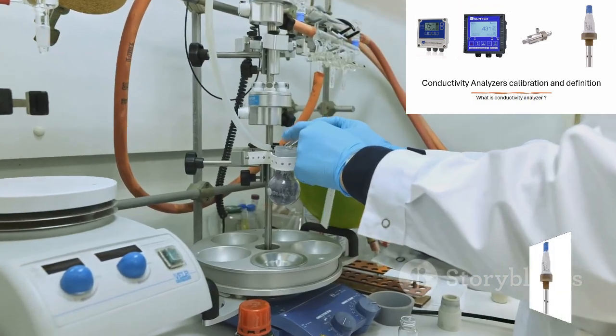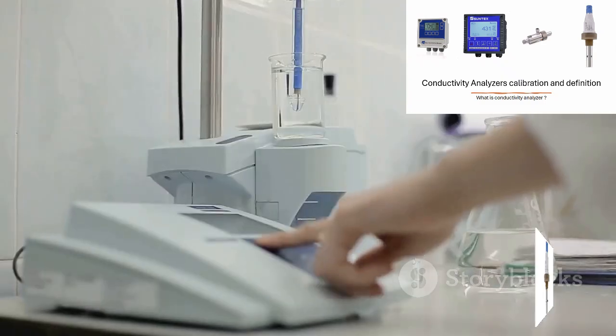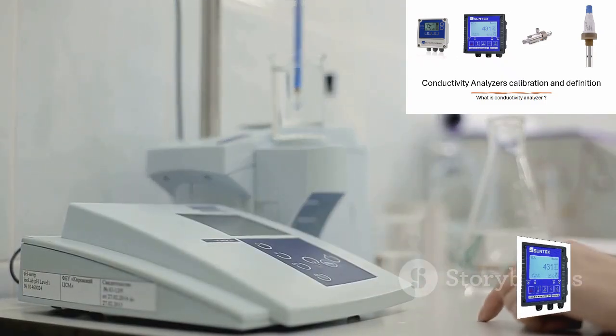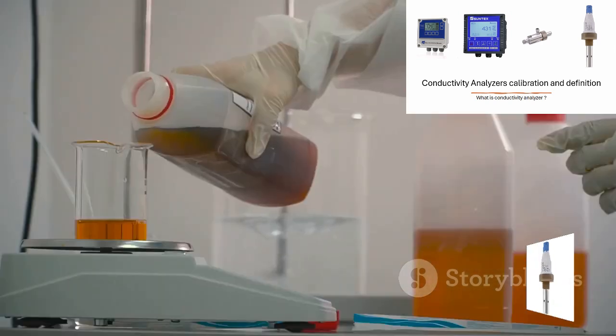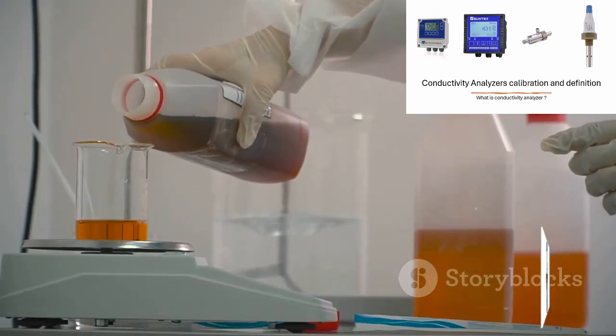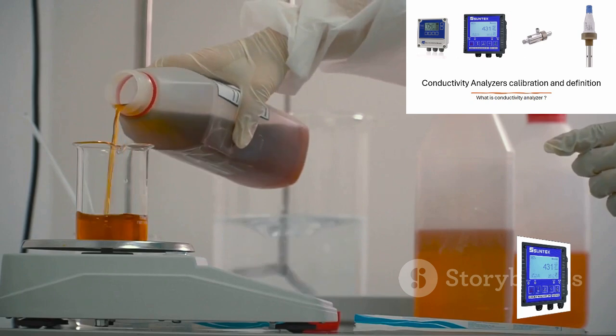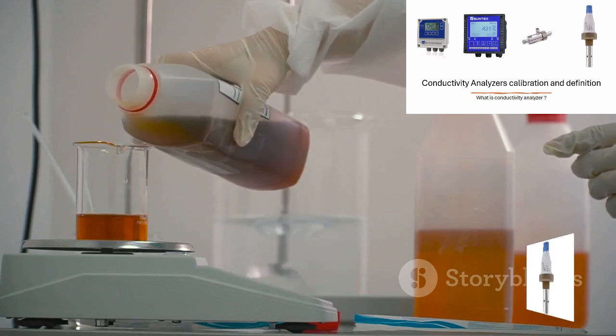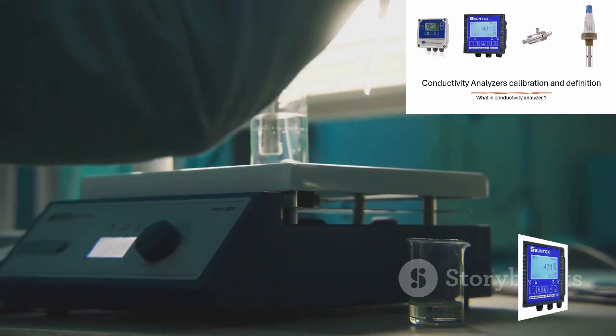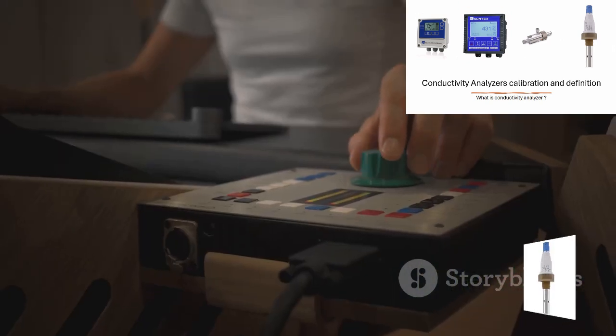So what exactly are we doing when we calibrate? We are essentially teaching our sensor what a specific, known value looks like. We use something called a standard solution, which is a special liquid with a precise, pre-measured conductivity level. By dipping our sensor into this solution, we can check if it's reading the correct number. If it's off, we adjust the sensor until it matches the standard.